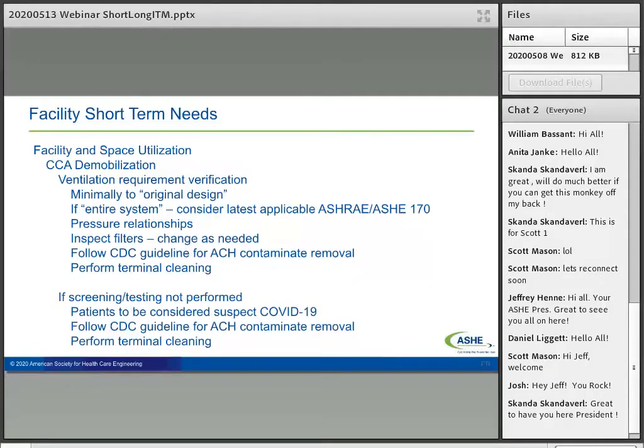For facilities and space utilization, a lot of changes were made to address the COVID situation. Ventilation requirement verification will be needed. Any spaces you converted back should, at a minimum, go to the original design. If you affected or impacted an entire system, you may consider moving to the latest applicable standards from ASHE 170, and make sure the pressure relationships match what the room will be used for.